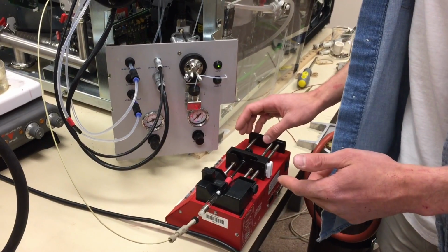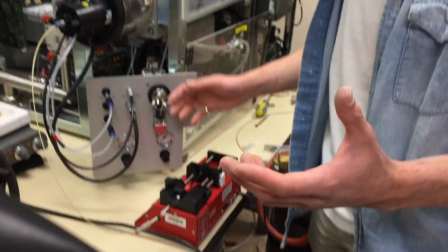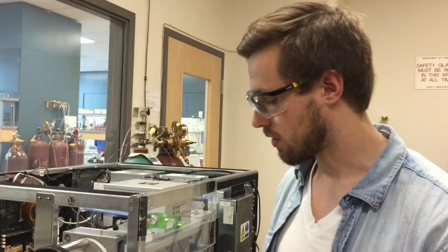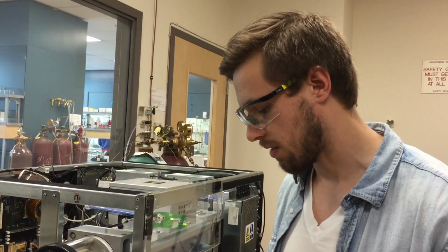So once we've got the syringe pump going, it's usually good to go at about 20 microliters a minute as for rate. It helps promote some of the aggregation for the larger peaks, and it feeds it into the instrument.